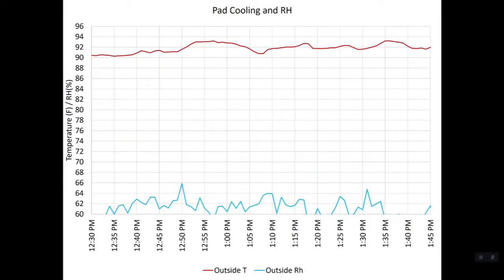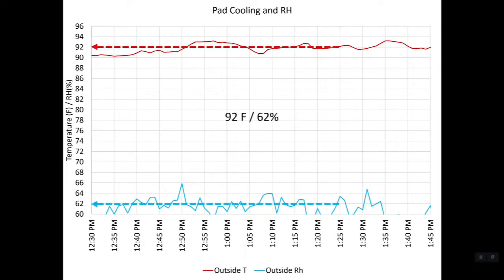This is the outside temperature and humidity last week on a farm where we are testing paper and plastic evaporative cooling pads. We are going to be showing some graphs today that have to do basically just with the paper pads. The outside temperature between 12:30 and 1:45 was around 92 degrees and the humidity was around 62 percent.